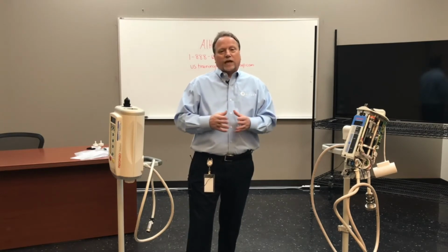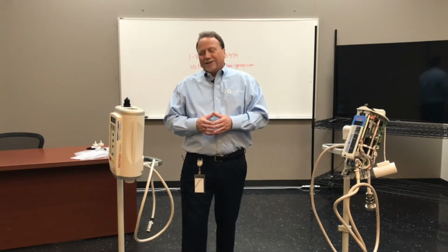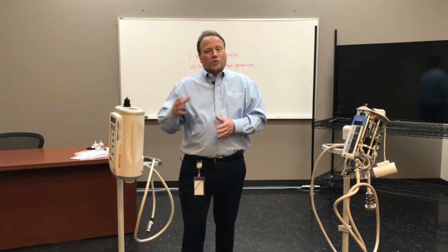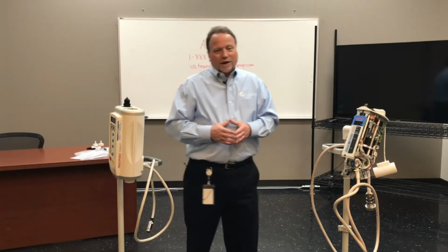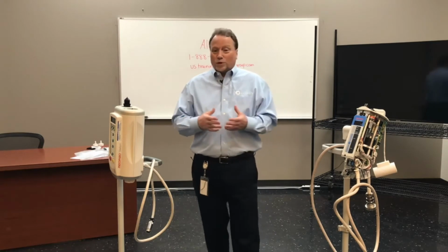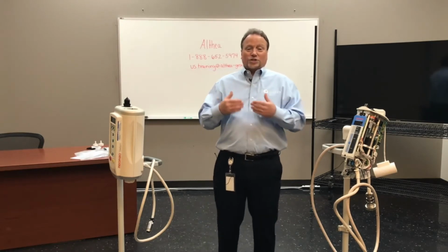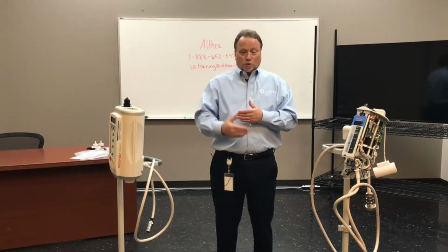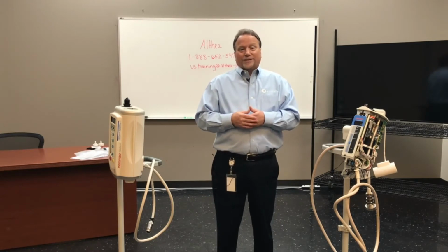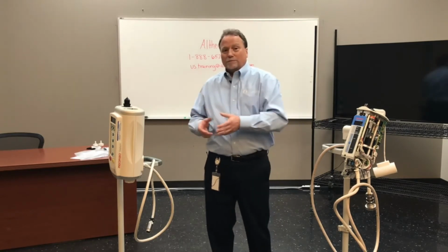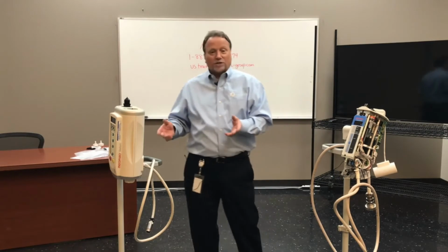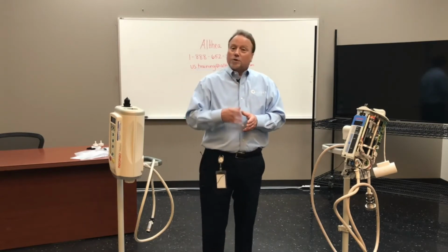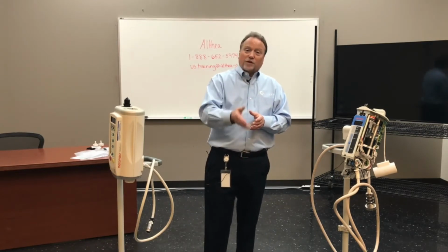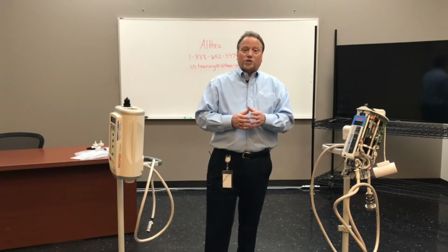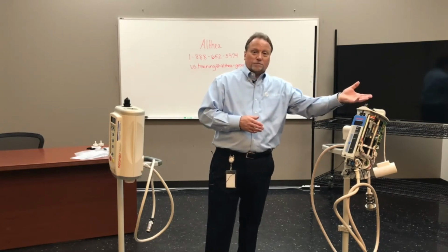The worst thing that can happen is you're doing the PM and it doesn't work right after. I've been in those shoes, and it hasn't really been anybody's fault, it's just the way it is. Something broke while you were doing the PM, had nothing to do with the PM, it just broke. Could be a connection, a failed connection that you found. But that's good, because you found that problem before it became an issue with patients.